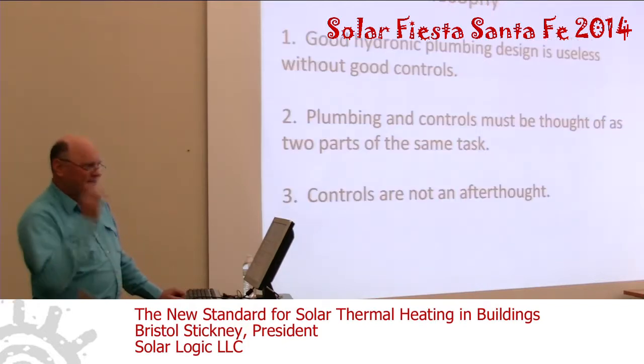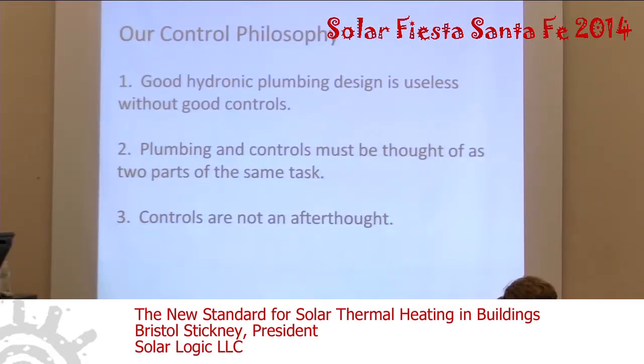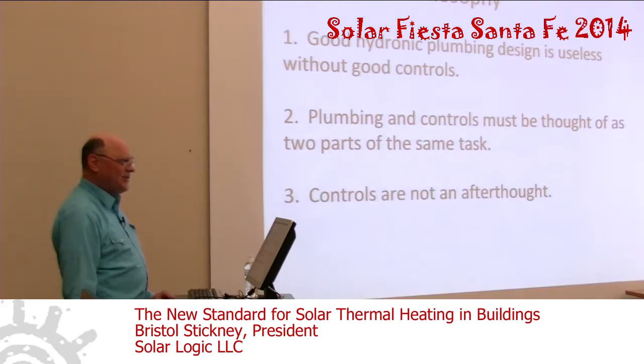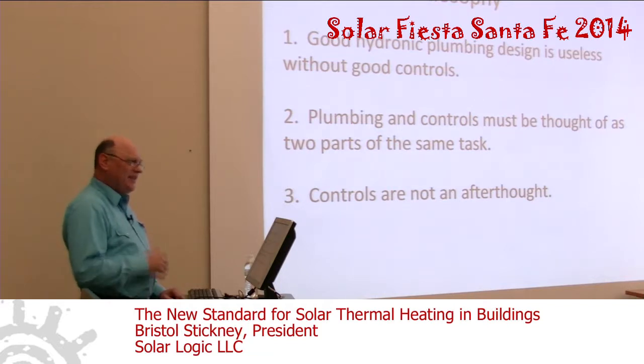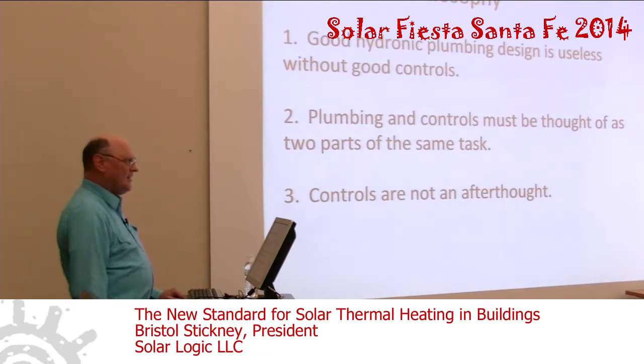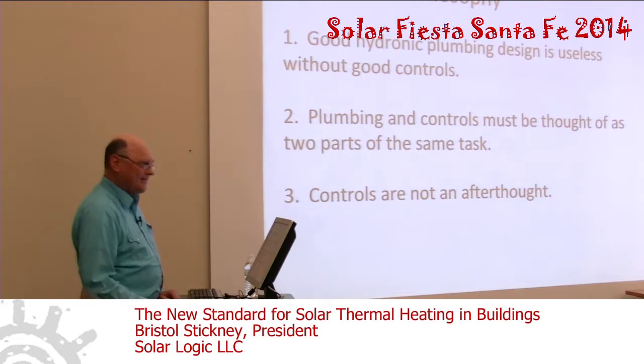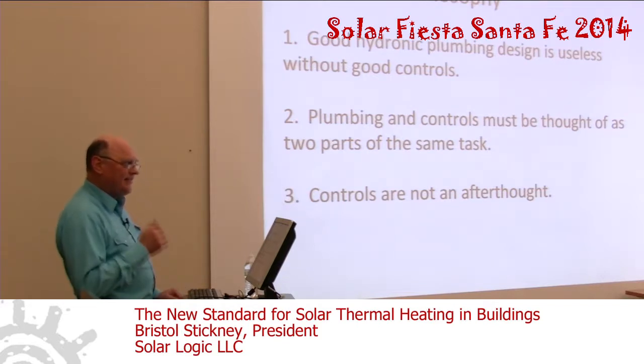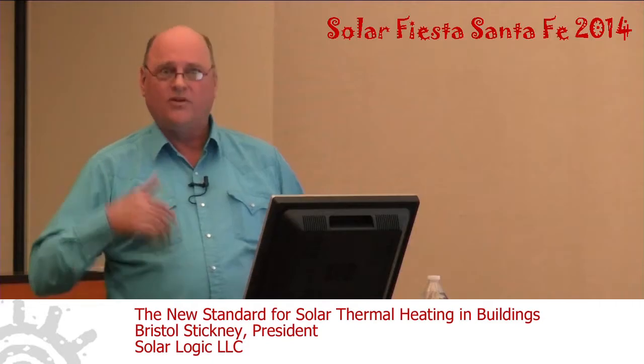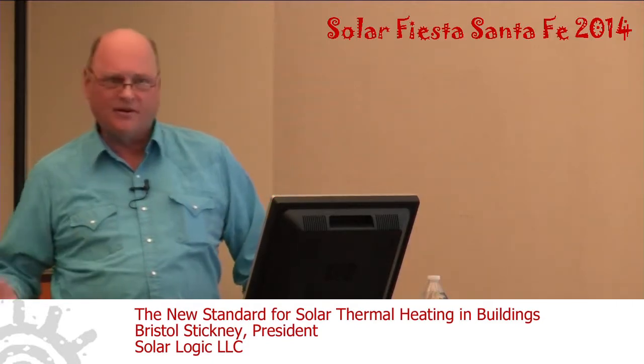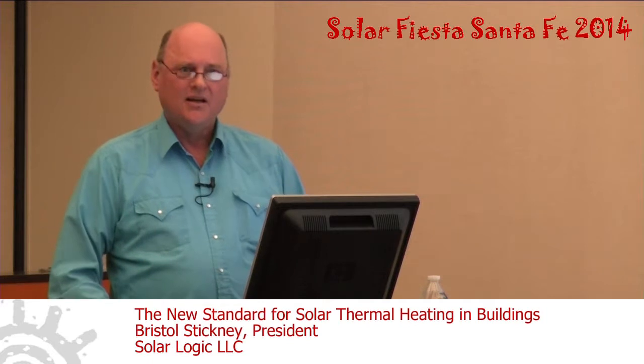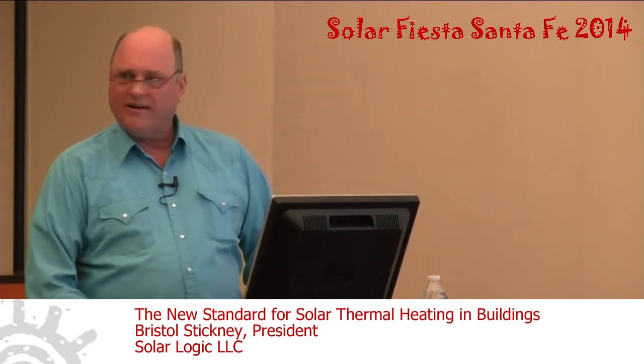So our philosophy when it comes to controls is that good hydronic plumbing design is useless without good controls. So plumbing and controls must be thought of as the same task, and controls are not an afterthought. Even if you're a good plumber and you decide to do some good plumbing, if you leave the controls till last, the controls will not work right. And that's been our experience over the last 20 years. If you treat the controls as if they're sort of an afterthought after you've done the plumbing, it will not work right. It just won't.